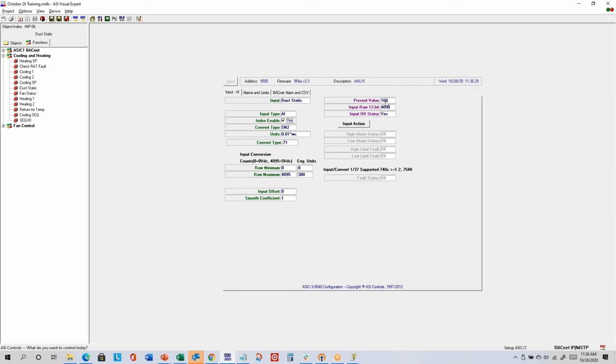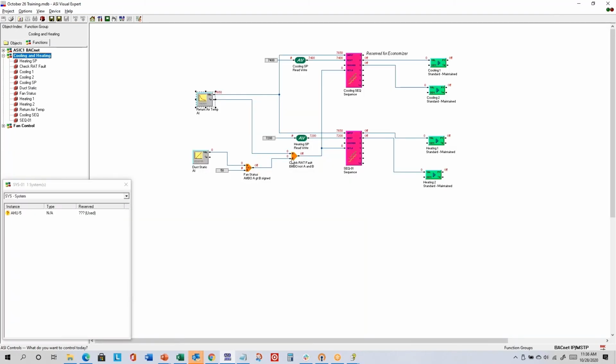If I change it to be less than 30, I'll just put in 0. Then the controller should think the fan dropped out. So the B handle is no longer non-zero, so that logic turns off. The interlock drops out, all the outputs immediately turn off. Once the interlock handle is reestablished, meaning it turns on again, then it will gracefully ramp up, honoring the delayed start time.